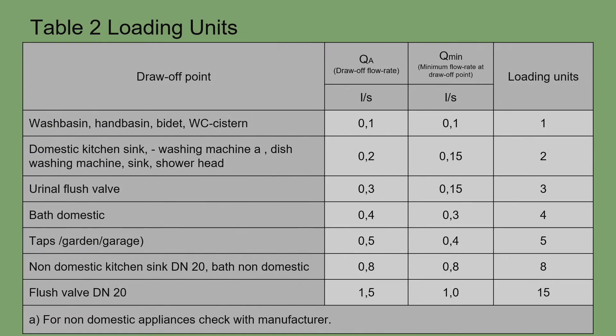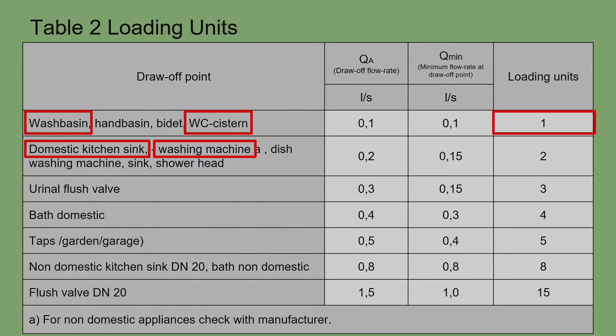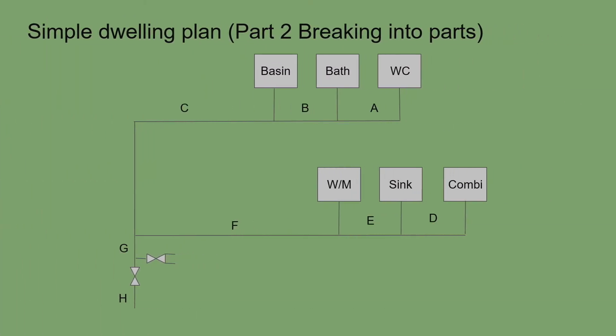Loading units come from BS EN 806 Part 3. In this property, a wash hand basin and a WC each have a loading unit of one. A kitchen sink and a washing machine each have a loading unit of two. The domestic bath has a loading unit of four. The combi boiler value must be figured out separately.